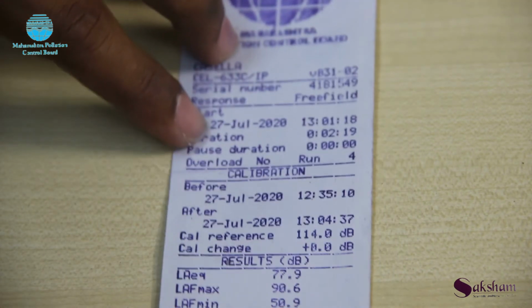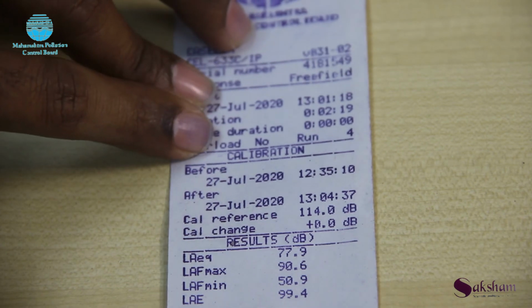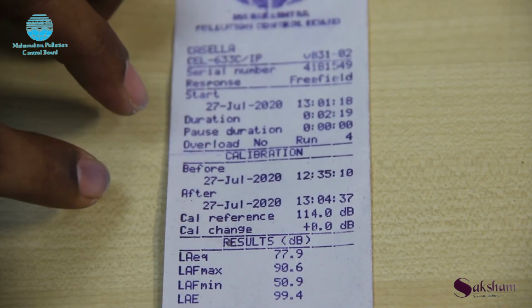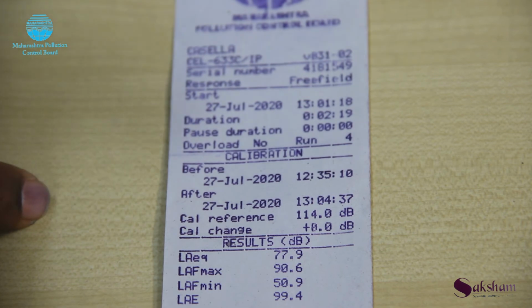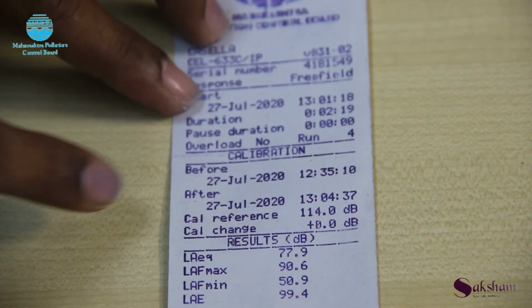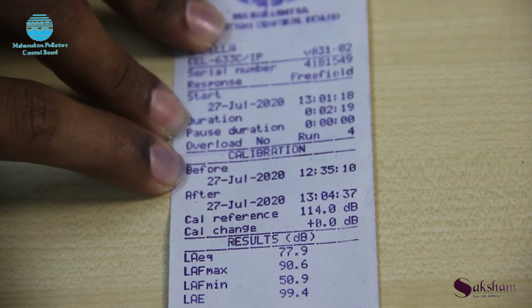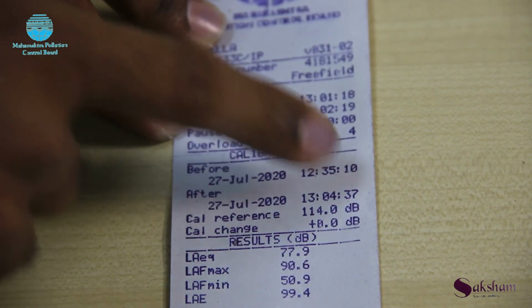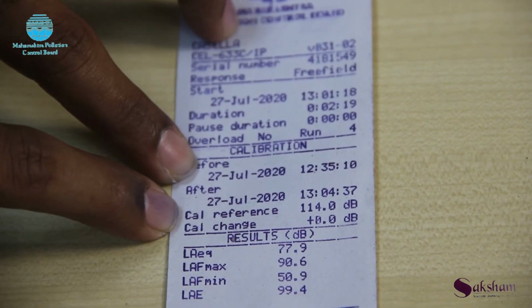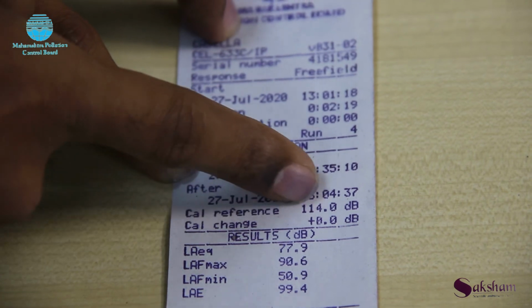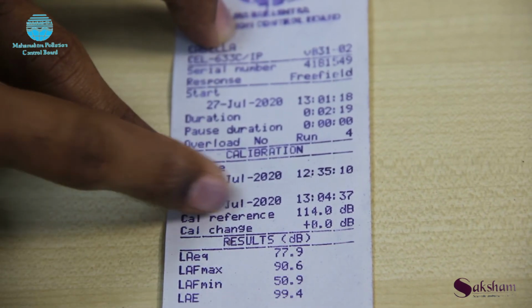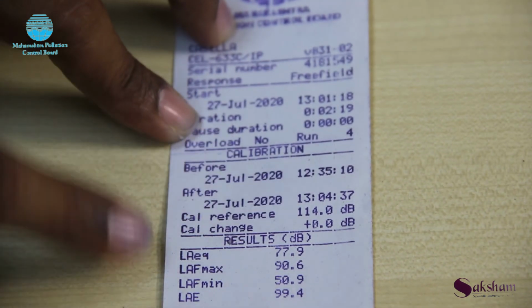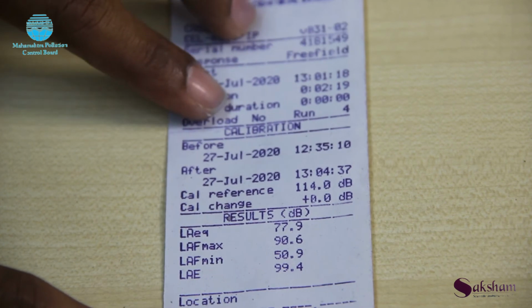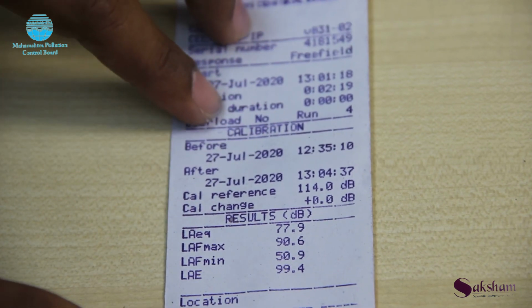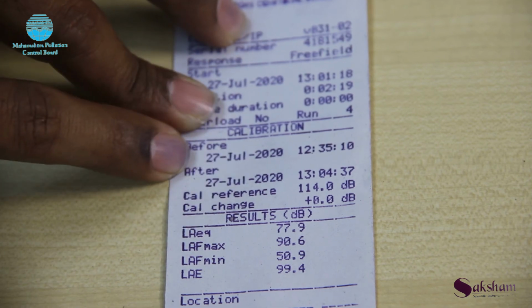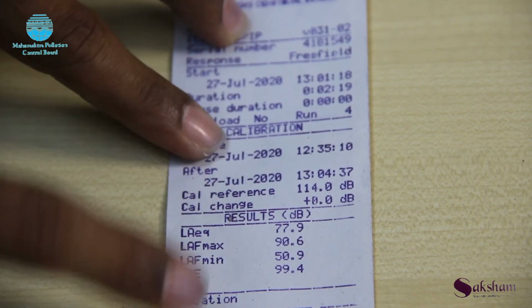Then below it is showing the calibration. We did the calibration before taking a reading as well as after completion of the reading. So that's why it is showing the before date and time and the after date and time. We use an acoustic calibrator, and the reference is 114, which is mentioned. This calibration confirms that your sound level meter is in good working condition at the time of taking a reading.